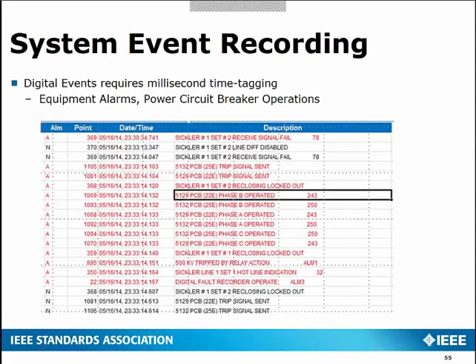A slower accuracy requirement that we've been using is recording the digital events within a substation. For instance, we need to know at least within a millisecond when a power circuit breaker interrupts the current, and when the trip gets sent to the breaker. This tells us if the breaker is getting slow or if it didn't operate correctly or if circuits aren't working correctly. So every fault that ever occurs is investigated, using these system event recordings, to ensure the correct operation of the system occurred.